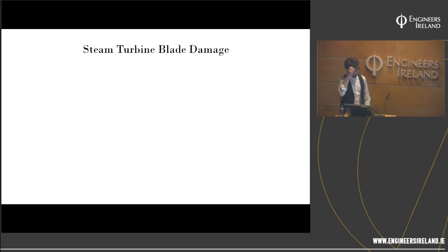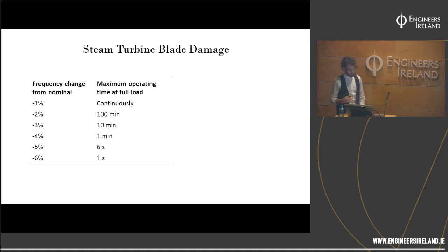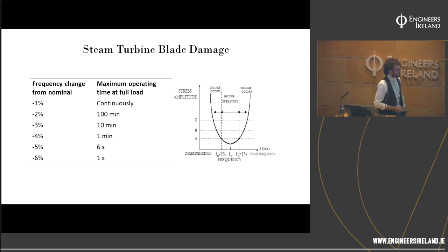Last one I'm going to talk about is steam turbine blade damage. So if you have extreme frequencies, you can actually get resonance in the blades because everything has a natural frequency. So as you can see, these are massive changes. You never really see these, but I think it's good to show that as the frequency gets more and more degraded, you have less and less time that you can operate the machine. It's just like a transmission line, which has the exact same impacts if it's overloaded. The reason is because once you move away from the nominal frequency, the stress amplitude increases, okay, and you can get degradation on the blade.